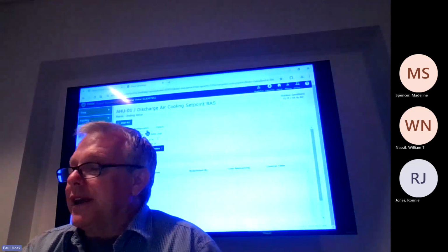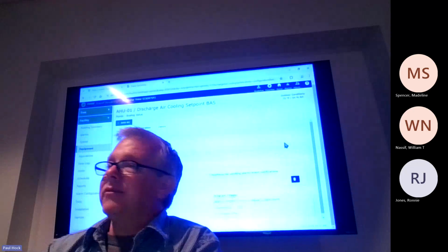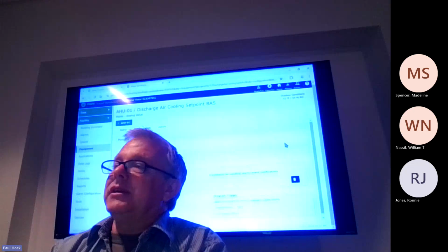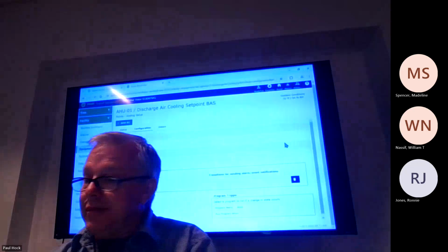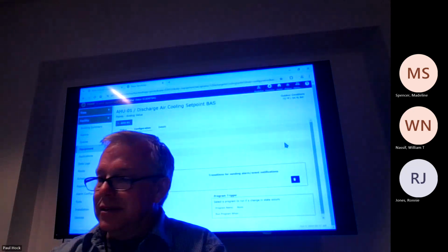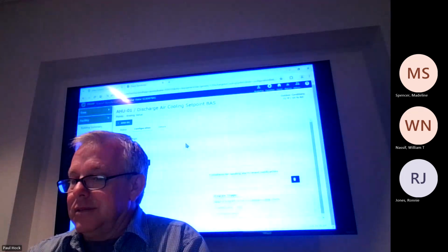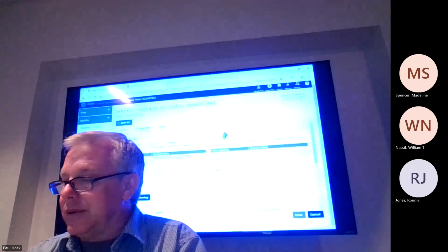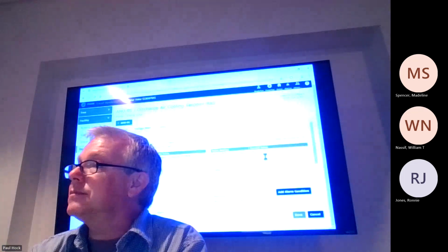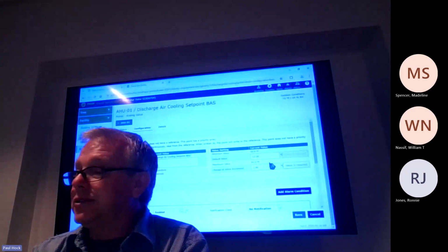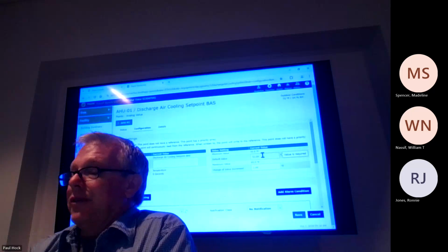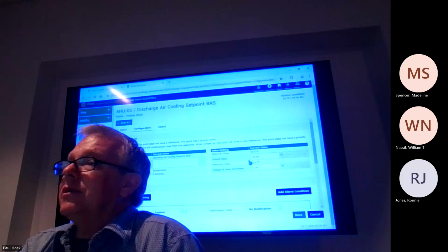And all that, I'll show you where all that's found. So all the settings in that controller, configuration here, is where you can set your alarms. And if you do override it, it'll tell you what the default value it's going to default back to is. So this default value right here is what it's going to default to. Now that's changeable. If you do want to make a permanent change, this is where you want to change it: your default value.